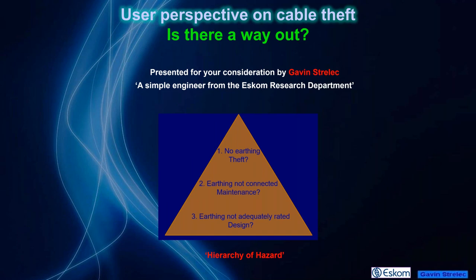When we look at the problem of cable theft, and earthing in particular, there's a hierarchy of risk we experience. The top tier risk is cable theft, or theft of earthing materials, because this renders the electrical system non-functional. Protection systems may not operate, meaning our infrastructure can literally burn, and we can lose transformers. We spend a lot of time on maintenance plans to keep the system in good order, and a lot of time on design, calculating whether we should use 70 millimeter square or 150 millimeter square conductors. But at the end of the day, if there's no cable in place, the whole system falls apart. That is the highest risk we face as engineers.